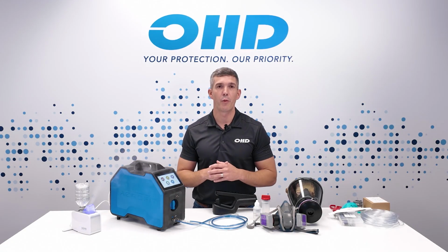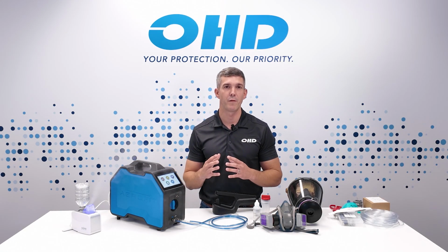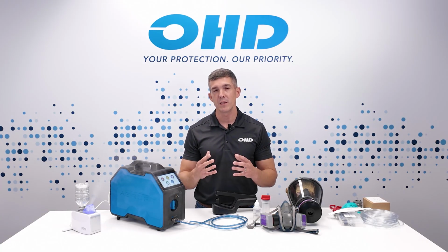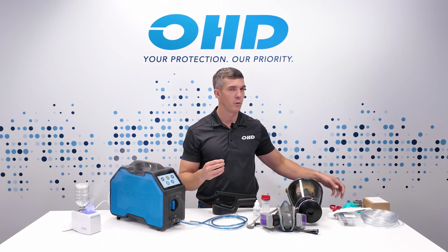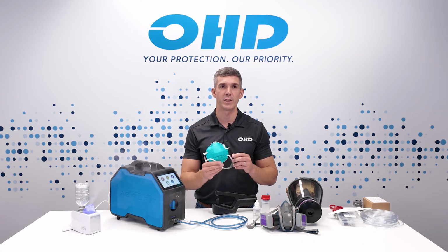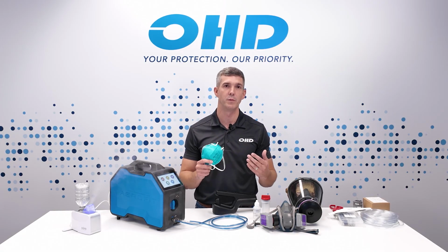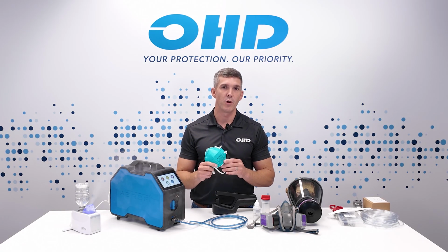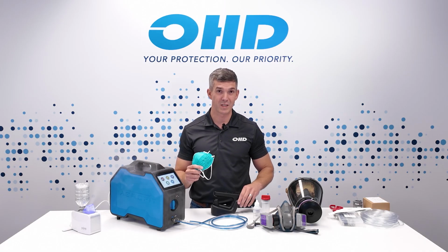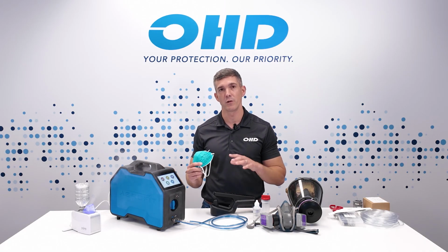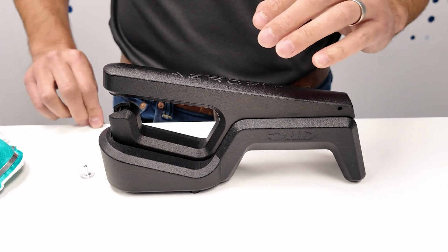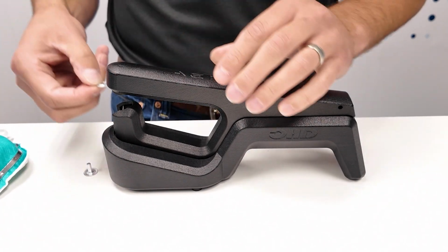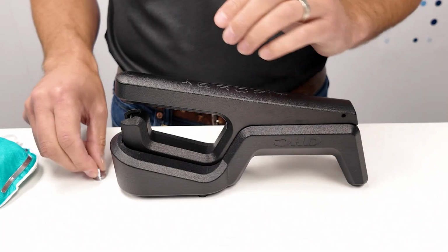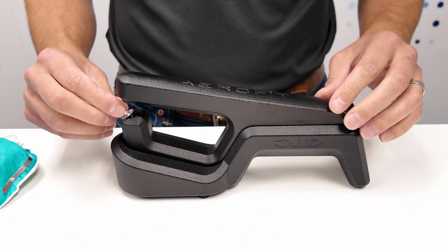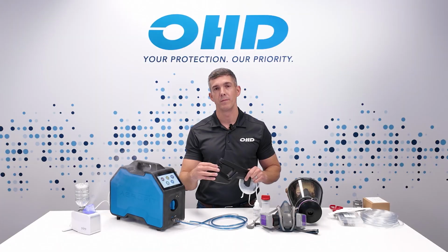Now let's go through probing and connecting to an FFR or FFP. Since this respirator is the filter, we need to probe directly to the respirator using our push nuts and probes. First, ensure your OHD probe insert tool or stapler is on a flat and strong surface. Take a push nut and attach it to the probing stapler magnet at the top, and then place the probe over the needle and be careful with the needle point.